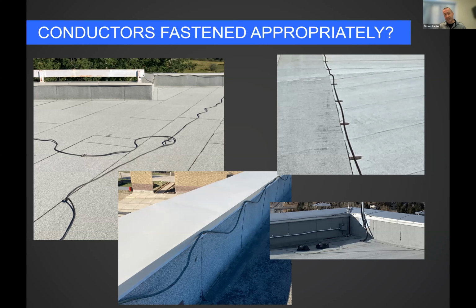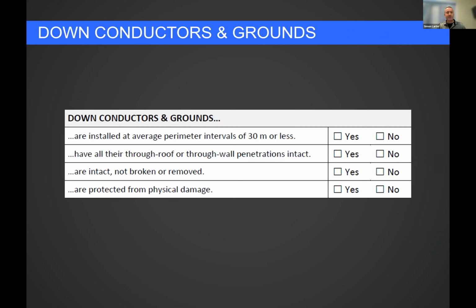And on the left-hand side, you can see there's no fasteners whatsoever. And you've got a lovely snake going on there at the parapet in the bottom picture. But over on the right-hand side, you can see a nice, tight, clean install on a penthouse parapet wall. You fasten it properly, you make it tight, and it's not going to whip around in the event of a strike. Down conductors and grounds.